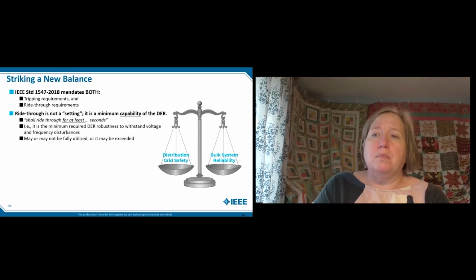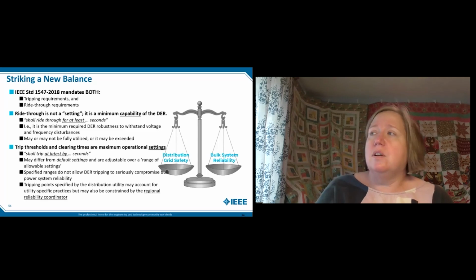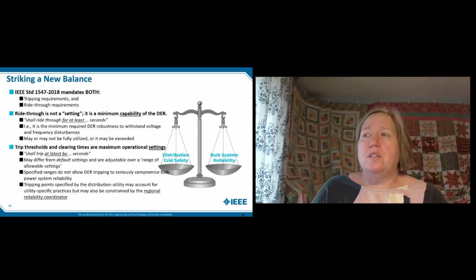It is the minimum DER robustness to withstand the voltage and frequency disturbances. It may or may not be utilized. It can be exceeded. So there are trip thresholds and clearing times that are maximal operational settings. So it shall trip in so many seconds. There are default settings. There are adjustable settings over a range of allowable settings. It's designed such that the ranges that are allowed do not allow for DER tripping to compromise bulk system reliability.